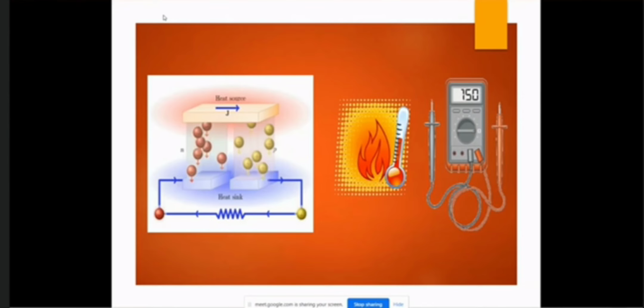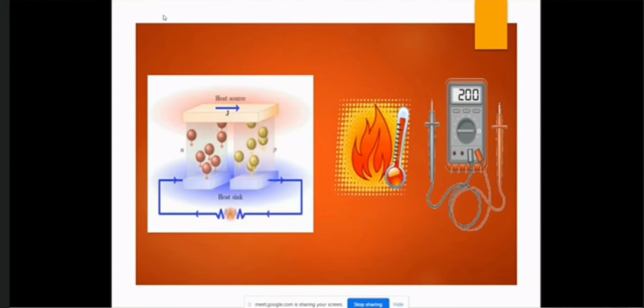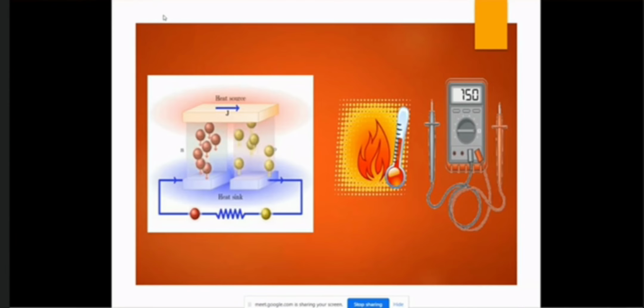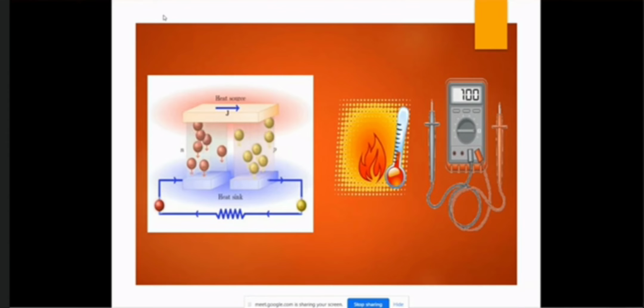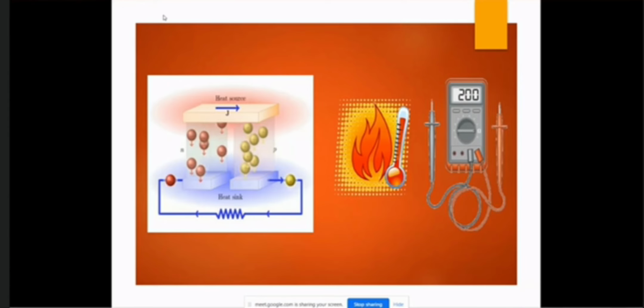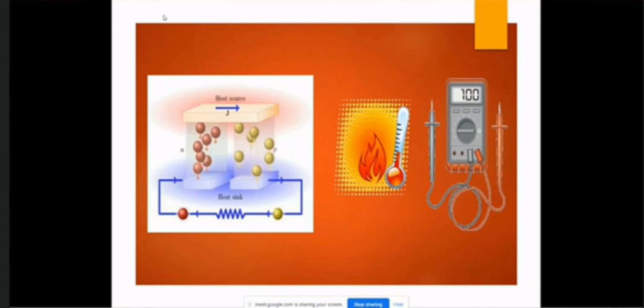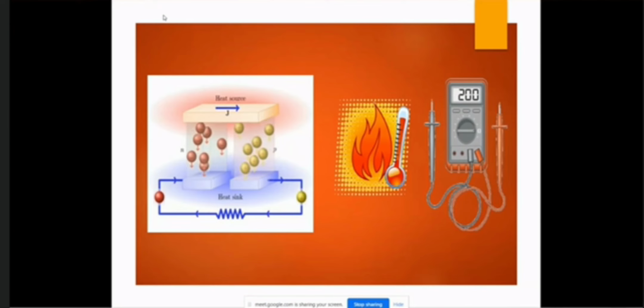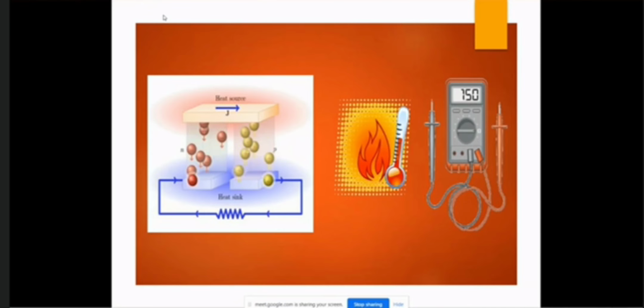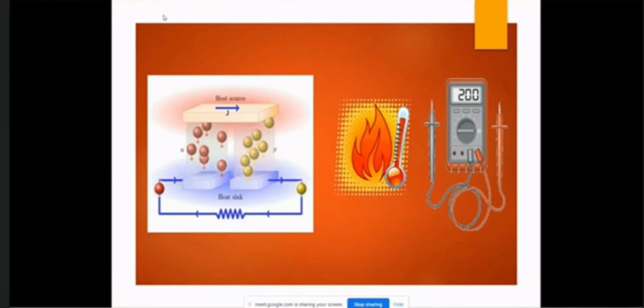This voltage lies within the range of a few millivolts for metals. Therefore, the signal is first amplified and then recorded with a precision voltmeter. The sample is pushed against a block of pure copper by a pneumatic cylinder. To ensure a well-defined and reproducible electric contact, the adjustable force is observed with a piezoelectric sensor.